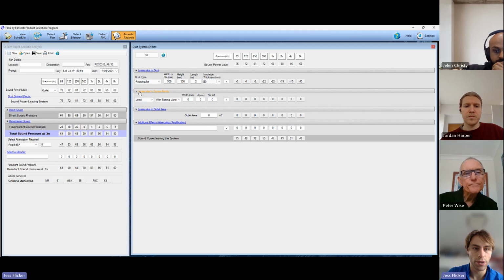Then, if you've got a square bend at the bottom of that riser, you can also model that - with turning vanes or without turning vanes. I'm not sure what you have, but you can put in width, the number of... So square bends also attenuate quite a lot, a little bit less of the low frequencies, but still help.